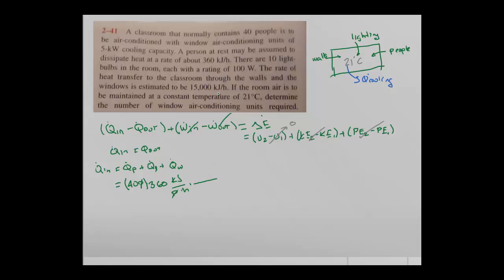We convert this to kilowatts: one hour is 3600 seconds, so we get the heat contribution from people in kilowatts. Now we add the heat from the lights. We have 10 lights, and each light consumes 100 watts. We have kilojoules per second, which is kilowatts, so we convert: one kilowatt equals 1000 watts.